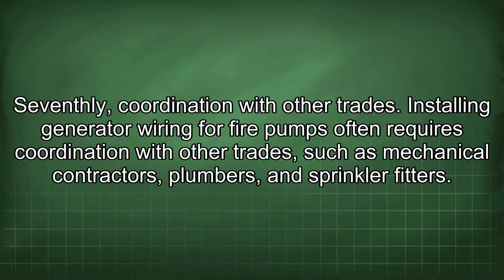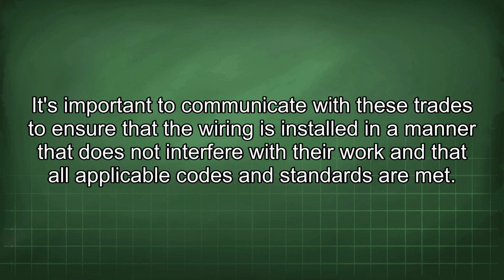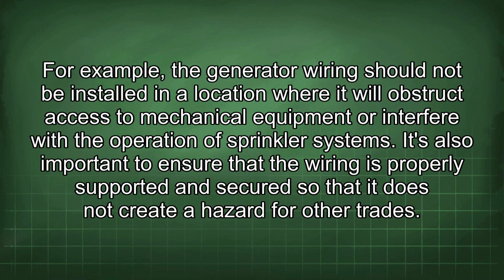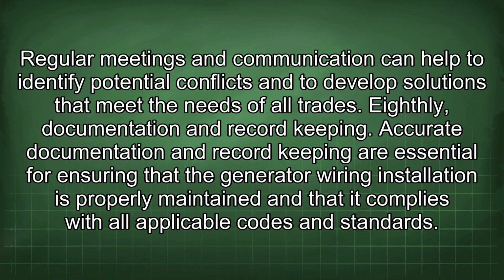Installing generator wiring for fire pumps often requires coordination with other trades such as mechanical contractors, plumbers, and sprinkler fitters. It's important to communicate with these trades to ensure that the wiring is installed in a manner that does not interfere with their work and that all applicable codes and standards are met. For example, the generator wiring should not be installed in a location where it will obstruct access to mechanical equipment or interfere with the operation of sprinkler systems. It's also important to ensure that the wiring is properly supported and secured so that it does not create a hazard for other trades. Regular meetings and communication can help to identify potential conflicts and to develop solutions that meet the needs of all trades.